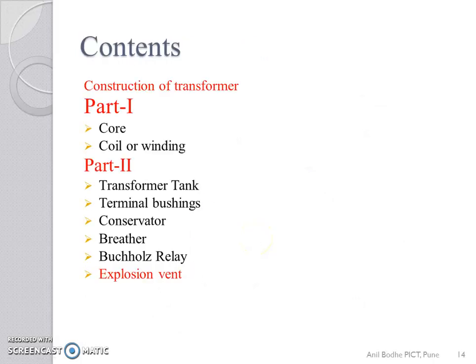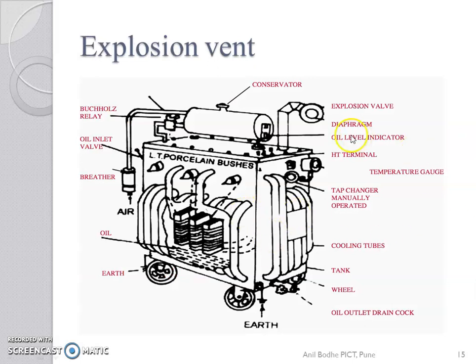Now, explosion vent. The vent pipe fitted on the upper surface of the tank is known as the explosion vent or relief valve. It is provided with a diaphragm made up of glass sheet, aluminum foil or bakelite sheet. In the event of the fault condition, if excessive pressure is developed inside the tank due to liberated gases, the diaphragm in the explosion vent bursts and releases the pressure, thus avoiding damage to the transformer. Thank you.